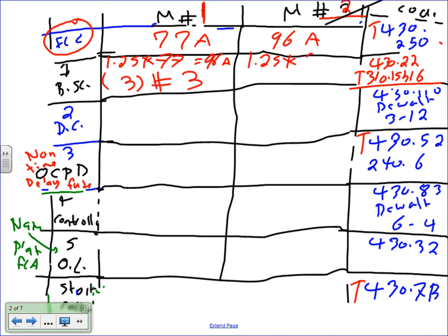Second one, piece of cake. 1.25 multiplied by 96. You're going to end up, if I did it right, with 120 amps. And that will translate into 3 conductors, number 1. Chris, are you coming with different numbers? Your calculator, not plugging in? Okay. That's it. Straightforward. Now, this is how we size the conductors.